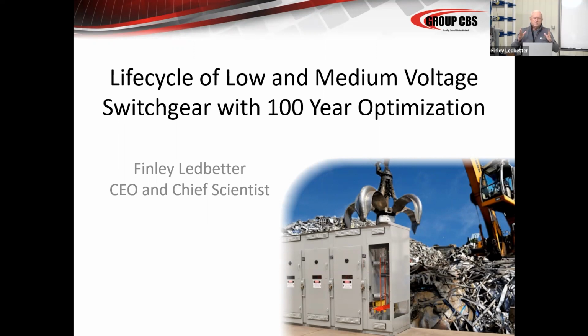So consequently, you don't do as much damage to the breaker every time you open and close it in repetitive applications. Where an air breaker, if you get a 15 kV or 5 kV heavy current, heavy MVA air breaker into a repetitive duty application, you just beat it to death because you're dealing with 1,000, 1,200, 1,500 foot-pounds of force, and you're jamming it together. There is sometimes a bias spring involved, or there is some cushioning, but still you just beat the contacts to death. Consequently, you have to take it apart fairly often and burnish the contacts, clean the contacts. You have to clean out the arc chutes.